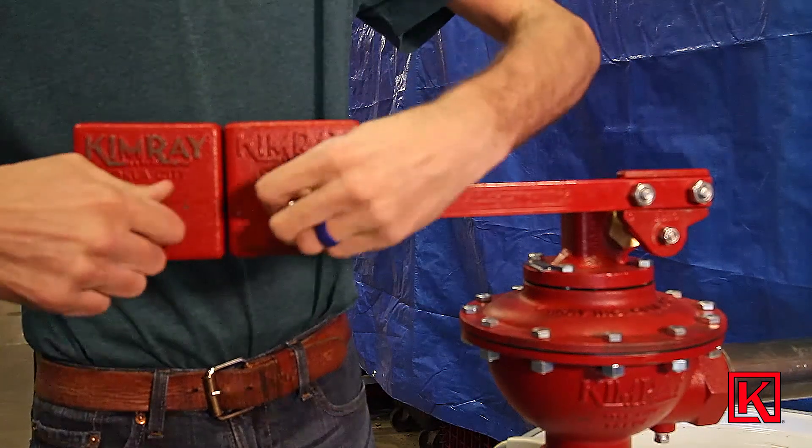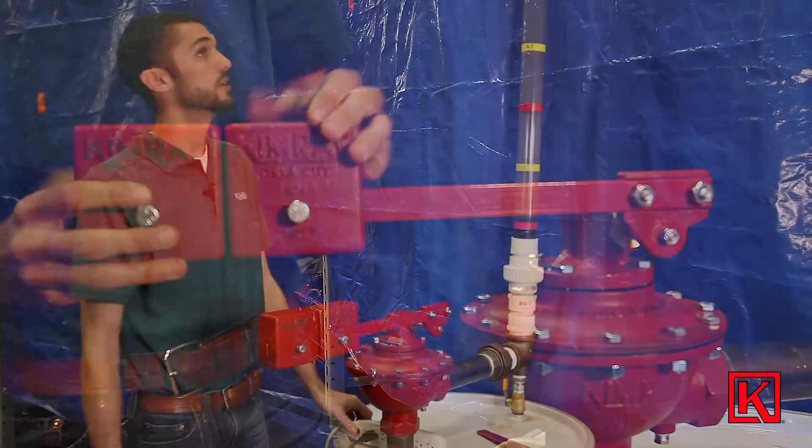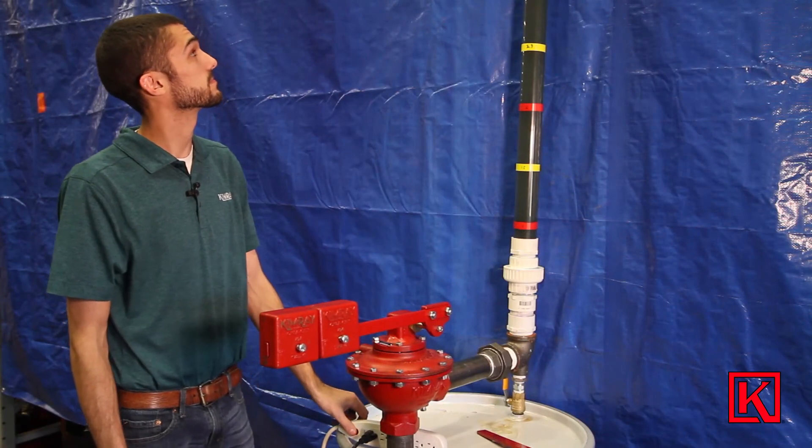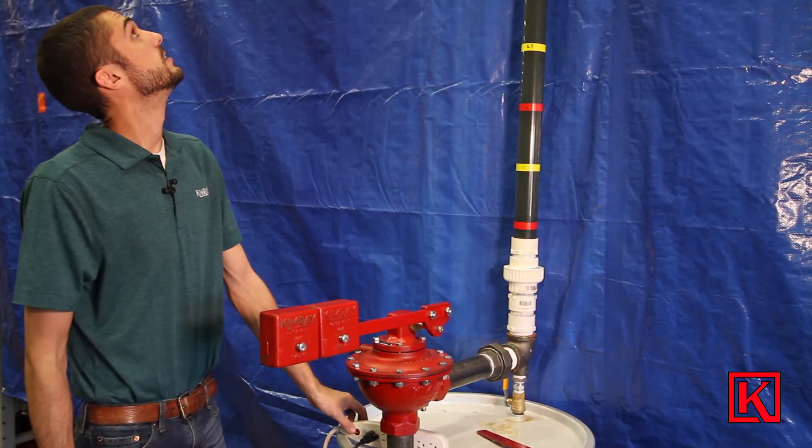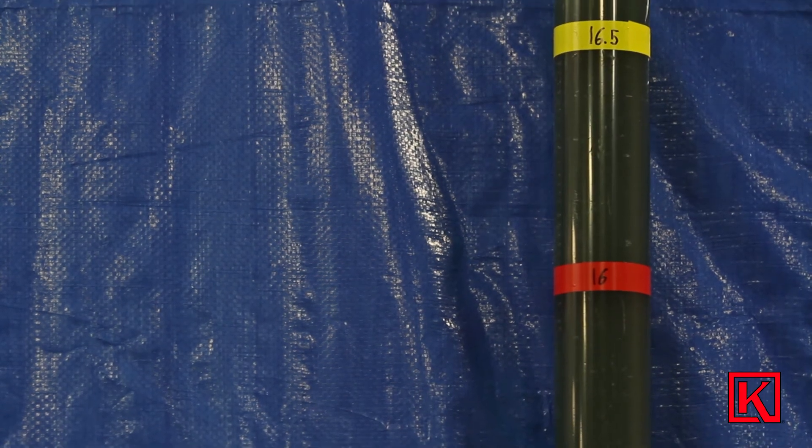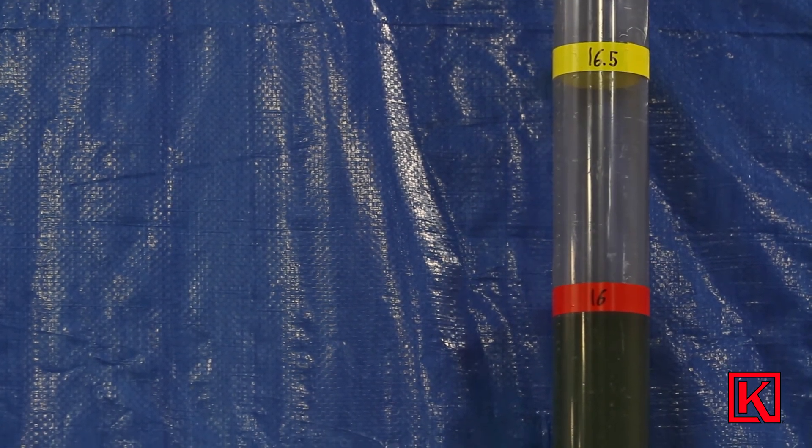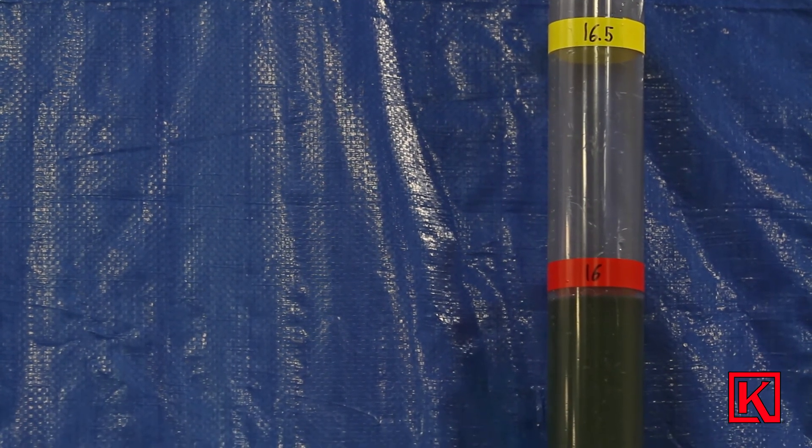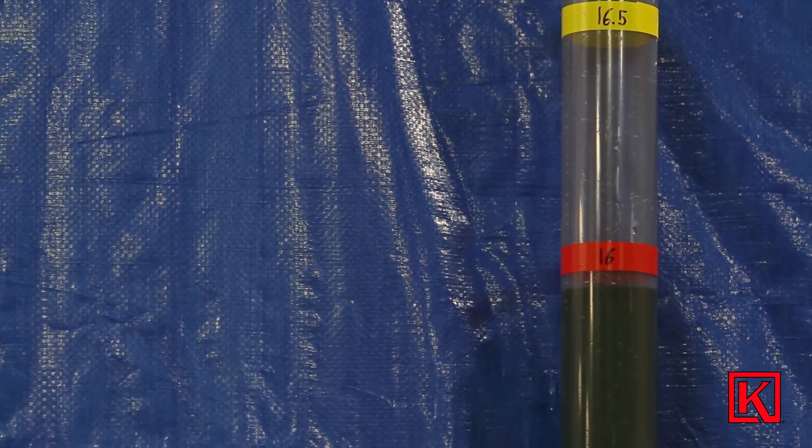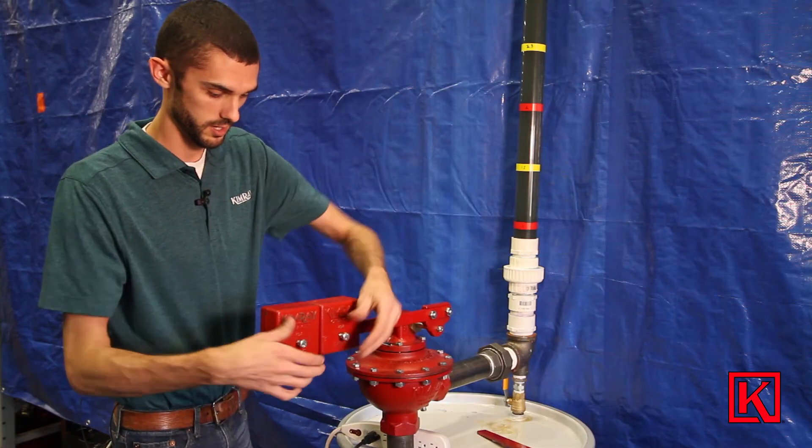Now we're going to use two weights on the 419L. We'll throw on the pump and see how much it holds. We're holding about 16 feet. That's going to be your maximum. Now we'll push them all the way in.